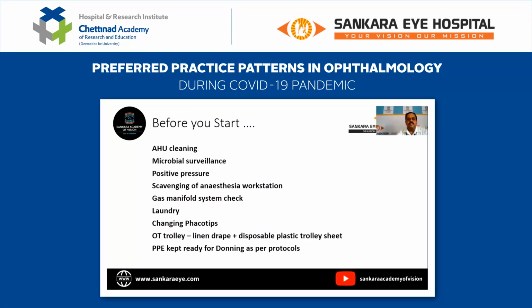In some of our hospitals, we've continued doing retinal surgeries and emergency procedures, but wherever we've had a shutdown, we've undergone this. Make sure that your OT positive pressure, temperature, and humidity are working. There is a scavenging system that you need to set up for your anesthesia workstation. Again, I'll show you a short video to describe what we have done. Most of us use central gas manifolds, so confirm there are no leaks, confirm that there is gas, and that the monitors are working well.